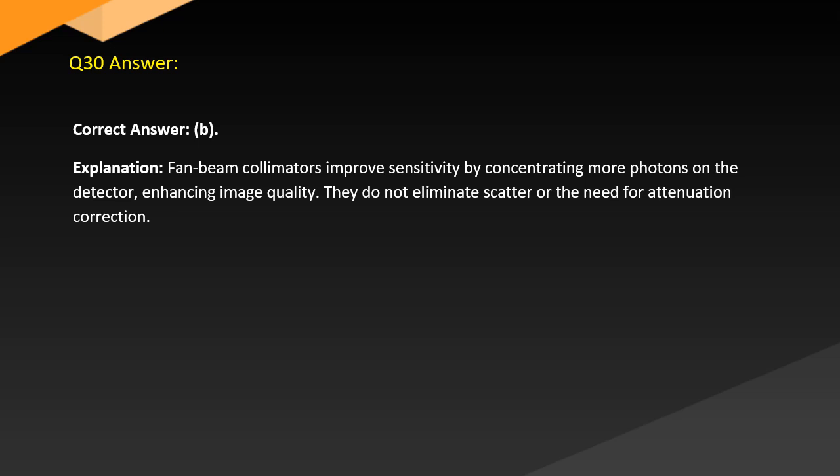Answer. Correct answer: B. Explanation. Fan beam collimators improve sensitivity by concentrating more photons on the detector, enhancing image quality. They do not eliminate scatter or the need for attenuation correction.